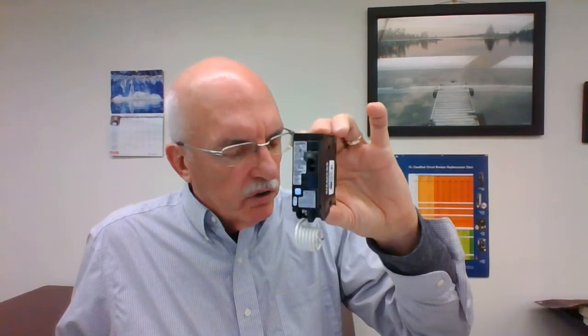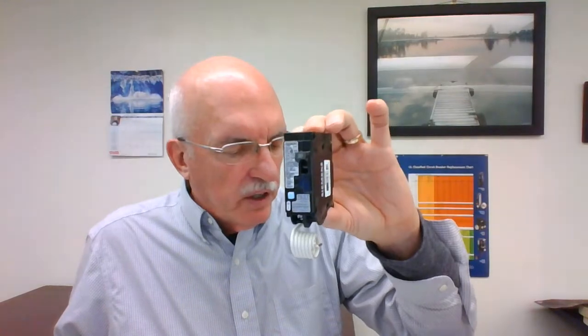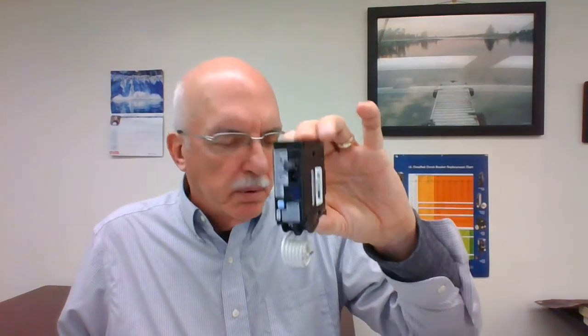And we get no relief from that, even though the circuit breakers will analyze their own circuitry every 5 or 10 seconds. Does not matter. We still have to test the units, the breakers, and the receptacles, monthly. And what we're doing there is we're testing the mechanical operation of the whole thing.